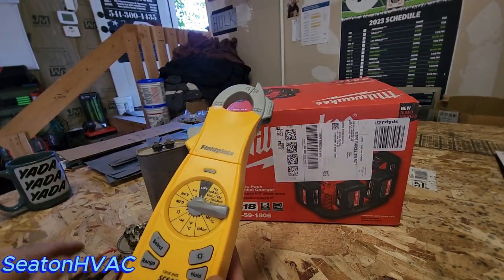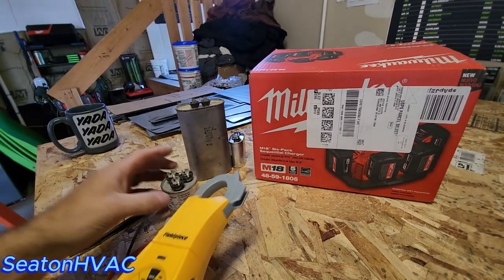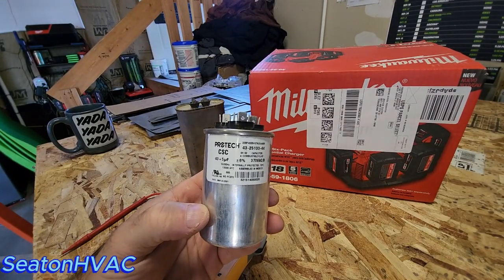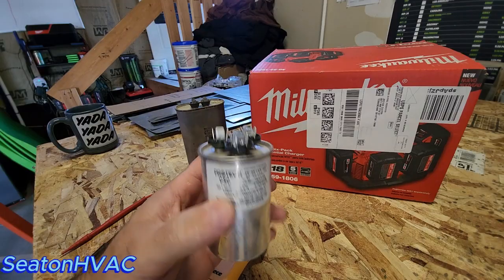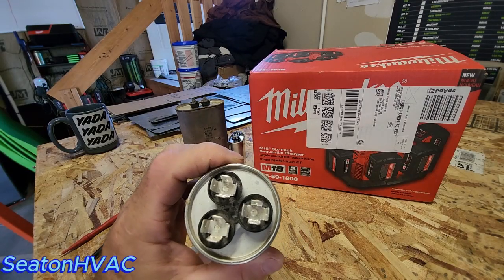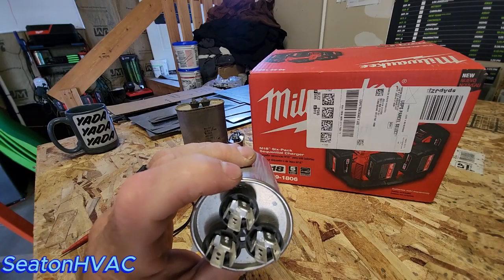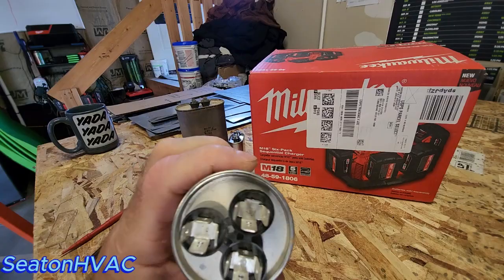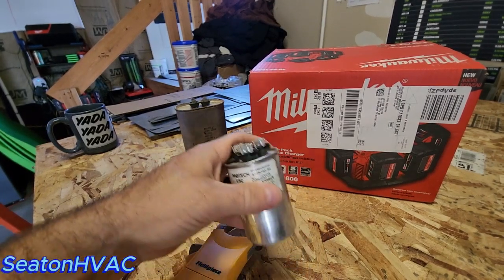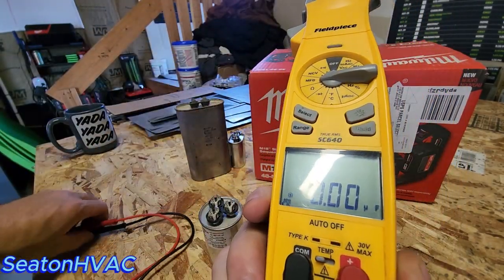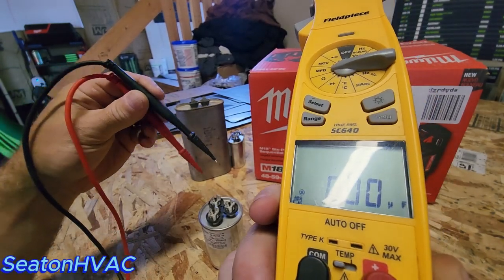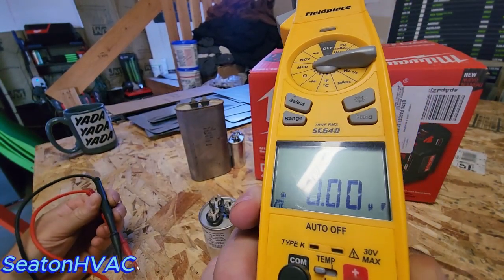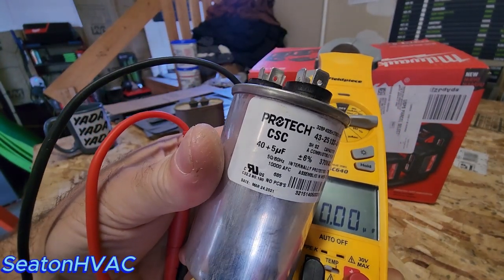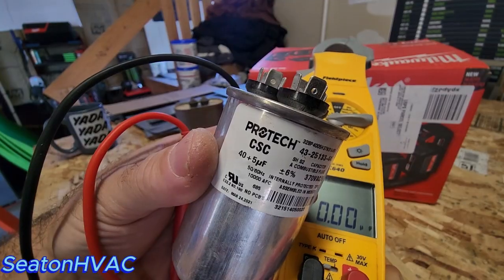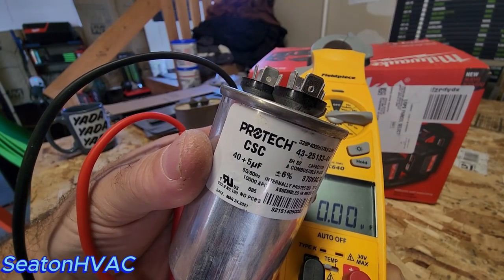Now let's move this over and go to the dual run capacitor. So this one does our hermetically sealed compressor. You'll have one terminal that's labeled herm, which is right here, one labeled common, which is right here, and one labeled fan. So what you want to do is take your leads again. Let's leave that up there so you can see what we're doing. And you're going to go from common to fan. Hold on, let's go over what this is first. This is a 40 plus 5. That means it's 40 for the compressor, 5 microfarads for the fan.